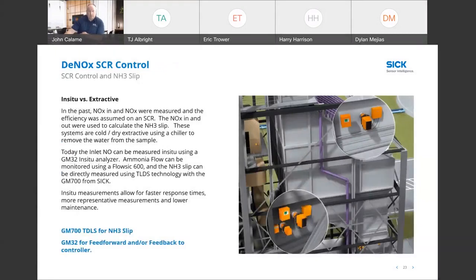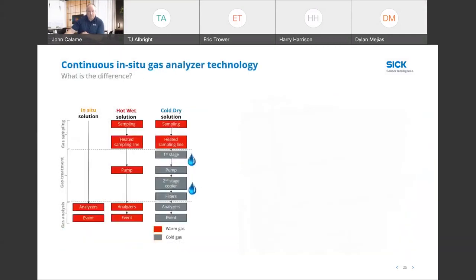So I talked through that one already, so I'm going to cruise past that. So what are the different methods or topologies for measuring NOx? We're primarily today talking about the in situ because we're trying to optimize control, and this gives you the fastest response. It's in the stack. We're not conditioning the sample, and we're not extracting the sample, so we don't have any sample lag times on that. So from left to right, the in situ would be our preference for a control strategy for the SCR or SNCR removal strategy.